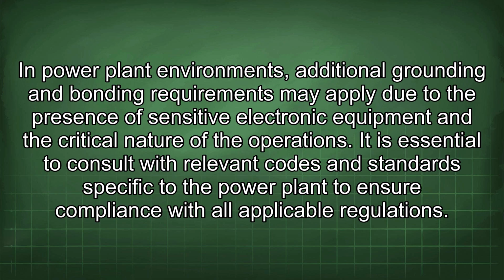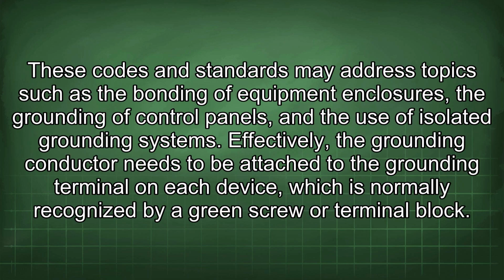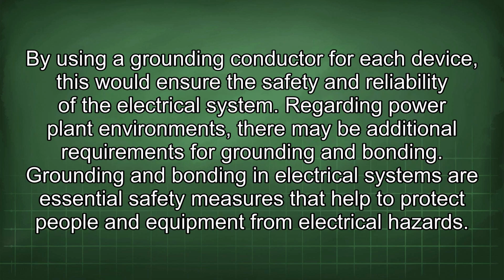It is essential to consult with relevant codes and standards specific to the power plant to ensure compliance with all applicable regulations. These codes and standards may address topics such as the bonding of equipment enclosures, the grounding of control panels, and the use of isolated grounding systems. Effectively, the grounding conductor needs to be attached to the grounding terminal on each device, which is normally recognized by a green screw or terminal block. By using a grounding conductor for each device, this would ensure the safety and reliability of the electrical system.